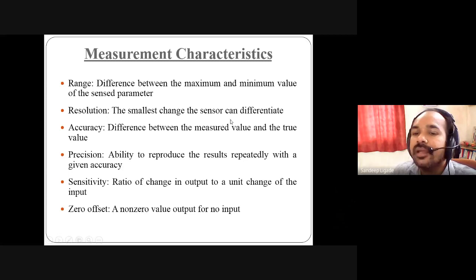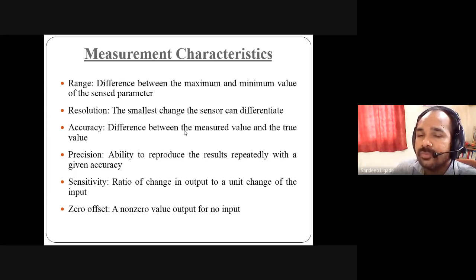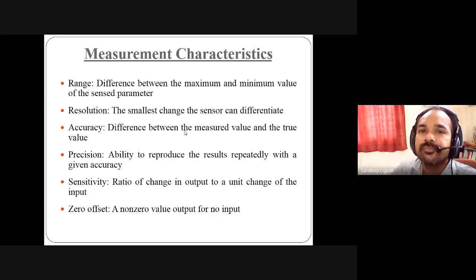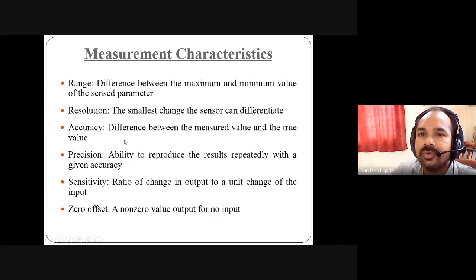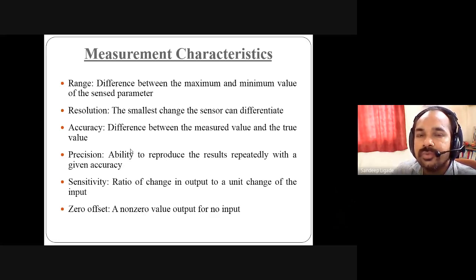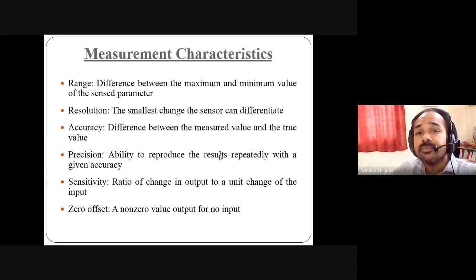Resolution is the smallest change the sensor can differentiate. For example, if we take a bucket of water from the ocean, we cannot visibly see the change, but some water has been extracted — that smallest change is what the sensor detects. Accuracy is the difference between the measured value and the true value — the sensor reading should be very close to the accurate value given by the manufacturer. Precision is the ability to reproduce that value again and again, very close to or exactly equal to the specified value.